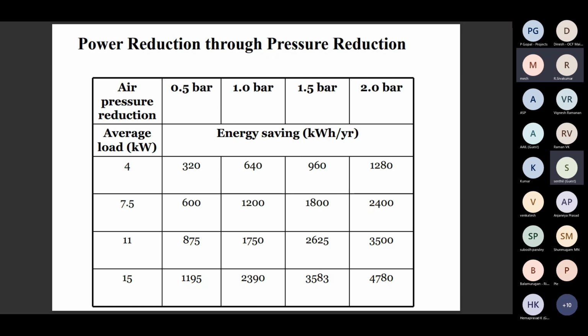So on the air compressor generation side, we must be very cautious. The optimum pressure should be set on the generating side. Most of the foundries and manufacturing industries are operating at 10 bar, loading at 8 bar and unloading at 10 bar, but the actual usage in the process area is only 6 to 6.5 bar. So they can reduce the generation side itself to 6.5 to 7 bar. If there are no losses in the pipeline and no air leakages, they can easily set loading and unloading below 6.5 to 7 bar, so they can achieve the best pressure at the farthest point of the air network within the foundry, and a lot of energy saving can be done. Next.